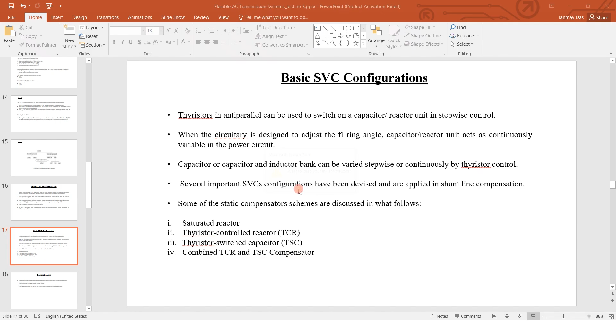This particular setup is done in such a way that it serves the purpose of both reactor compensation and capacitor compensation. So the combined TSC and TCR are the optimal solution in the majority of cases. Depending upon the requirement of reactive power, as I've told you, when there is a requirement to supply reactive power, we need a capacitor, and when we require the consumption of reactive power, we need a reactor. So based on the requirement, the optimal solution is the combination of TSC and TCR.